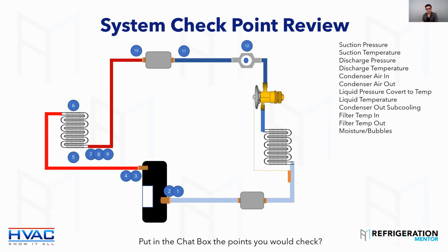When I worked for the compressor manufacturer, I saw it after a year, after 2 years, compressors failing because of that day one install, even though the compressor didn't fail for 2 years down the road. You can tell that by looking inside a compressor. It's pretty cool when you understand that stuff. Sight glasses are a friend of the technician because it's a window into the system. Well, not the only window, because you've got oil sight glasses and stuff like that.